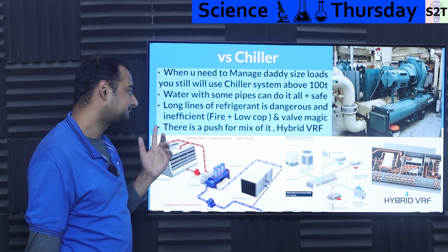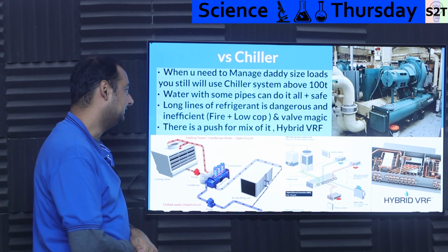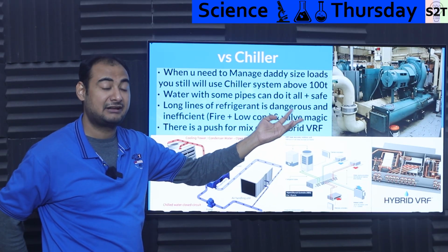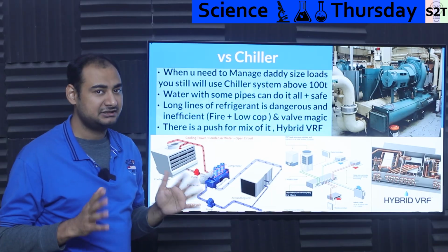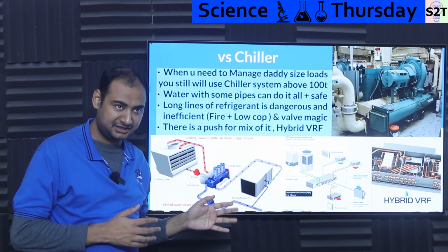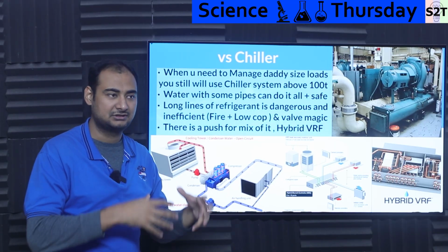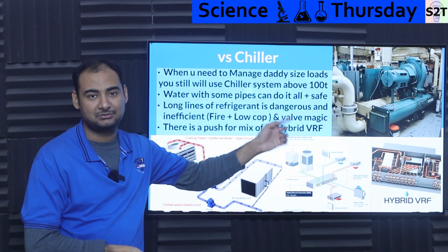So that is there. And long refrigerant line is something that you cannot just ignore. And chillers also have this advantage that you can use those sort of flammable system. Why? Because they are generally put in mechanical room. Meaning, if an engineer did his job right and they are assuming this is a mechanical room, they will design it to go boom. As in, like kitchen. Like if you have kitchen and you have propane and butane, kitchens are designed to handle fire hazards. This will be designed in such way.